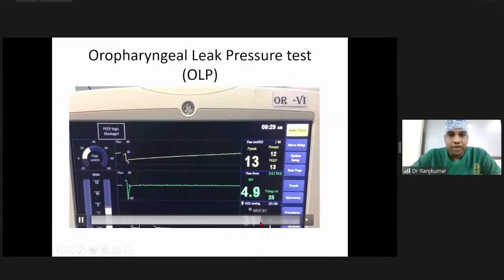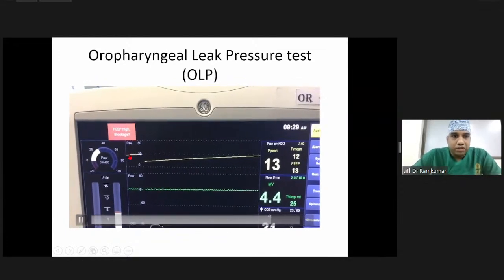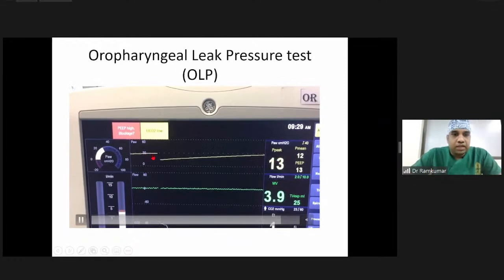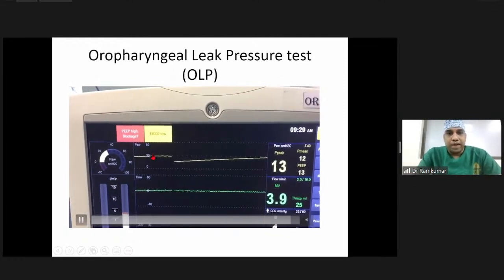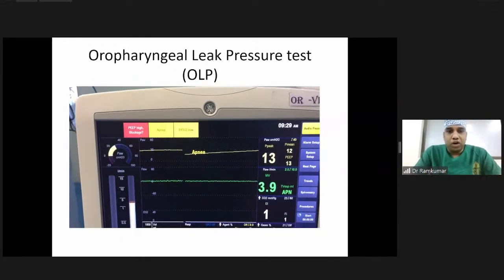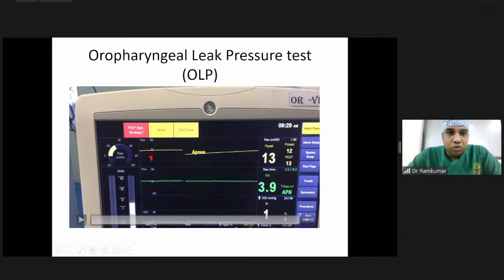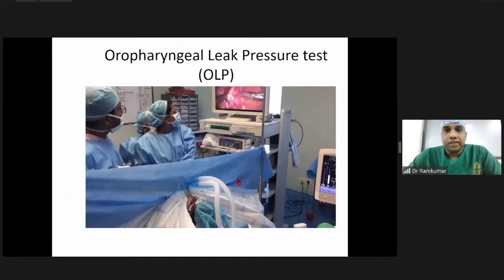So at one point, it is going to reach the plateau. See, can you see the plateau at the 30 centimeter? If at one point it reaches the plateau, or it's going to leak. When you hear an audible leak, or you achieve an equilibrium with the system, that is at 30 centimeter of water, that is the oropharyngeal leak pressure of the particular device. Here, the oropharyngeal leak pressure of this particular device, the ProSeal, is around 30 centimeter of water.